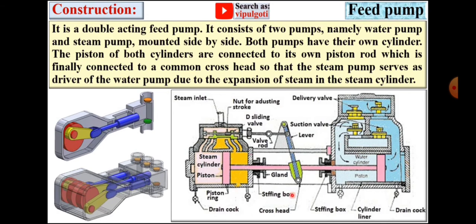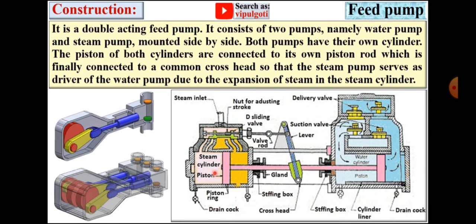Both pumps have their own cylinder. Here you can see the piston of both cylinders are connected to its own piston rod, which is finally connected to a common crosshead, so that the steam pump serves as a driver of the water pump due to the expansion of the steam in the steam cylinder.